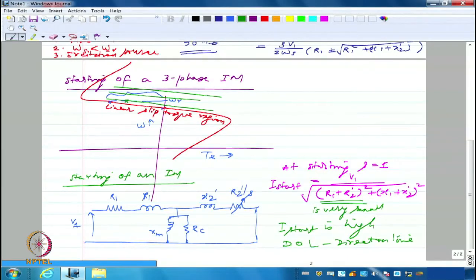It won't help if we try to start, say, a 100 kilowatt induction motor directly on three-phase supply, because the current drawn can be 5 to 8 times the full load current. If full load current is 10 amperes, we might draw 70 to 80 amperes directly online. So power system authorities limit the rating of motors allowed for direct starting, generally up to 10 kilowatt, at most 50 kilowatt. Beyond that, direct online starting risks having your power supply revoked, as it affects other consumers.